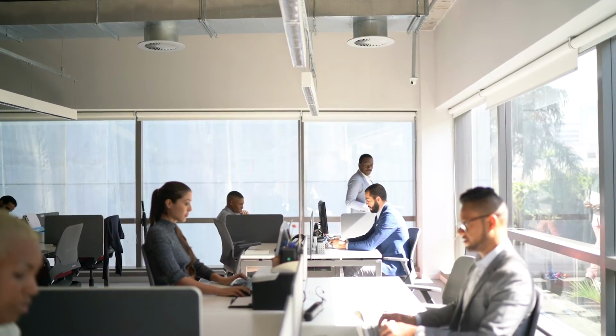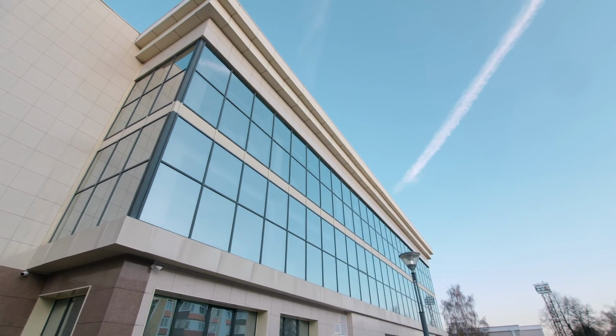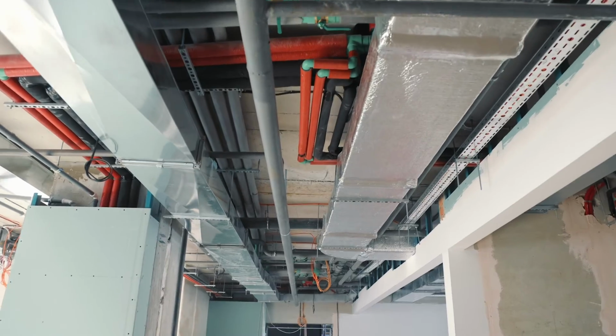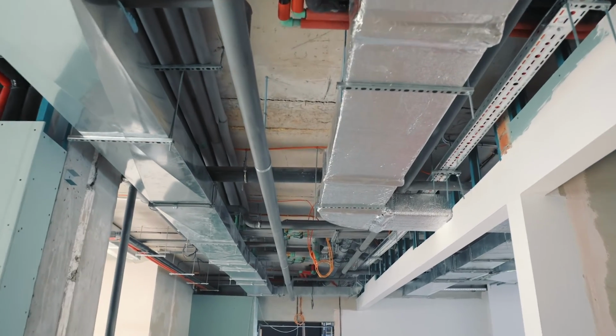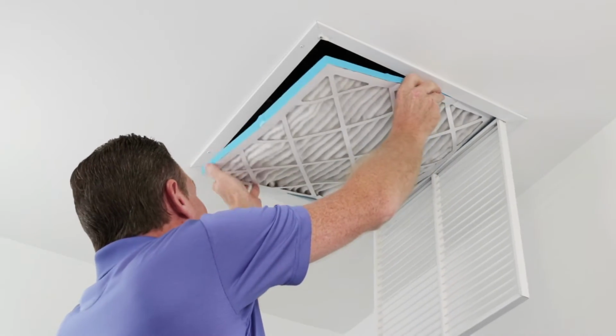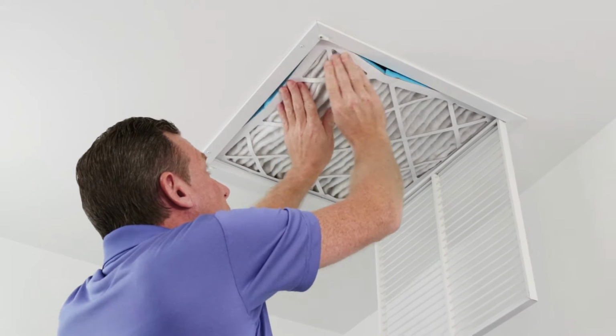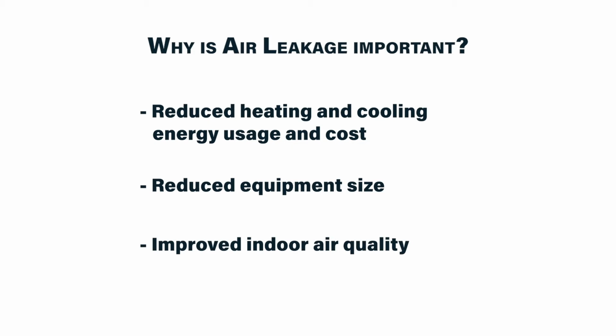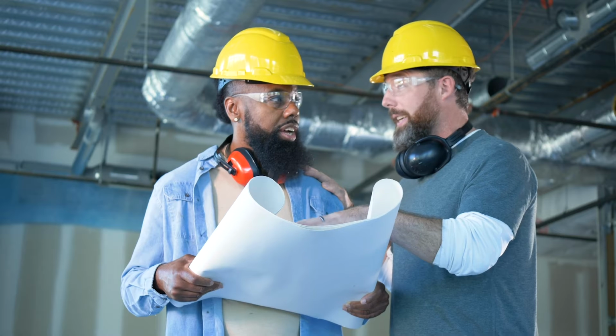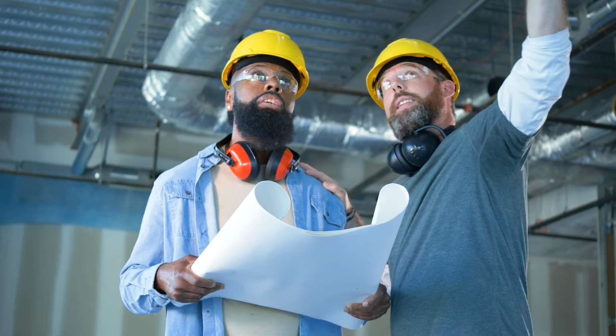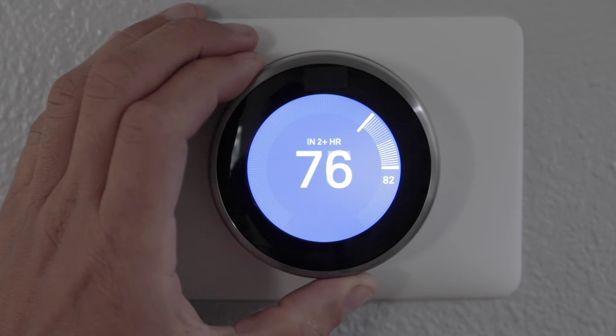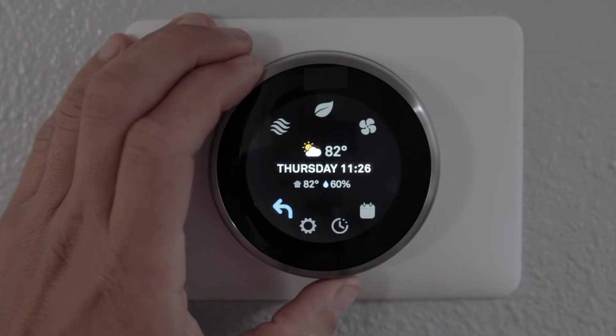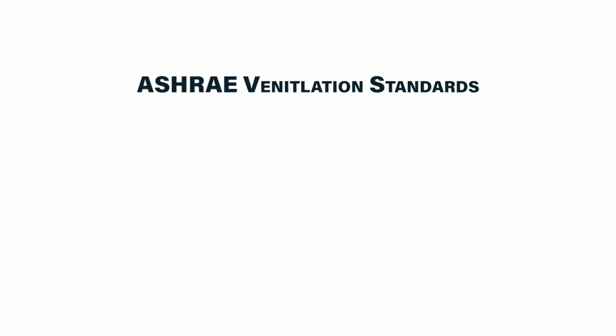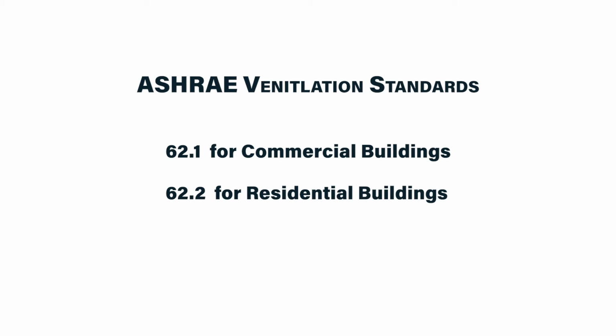for all occupants. As the building's envelope gets tighter and the air leakage is reduced, there is an increase in the amount of ventilation air required. This allows for more of the fresh air that occupants breathe to be filtered, decreasing the number of pollutants and pollen within the building envelope. Make sure to follow all mechanical ventilation codes, conduct testing and balancing, and commission controls to maintain proper outdoor air rates. Also consider referencing ASHRAE's ventilation standards 62.1 for commercial buildings and 62.2 for residential buildings.